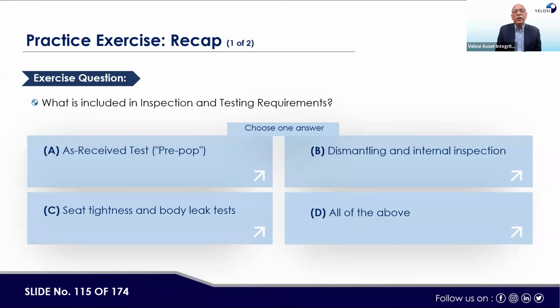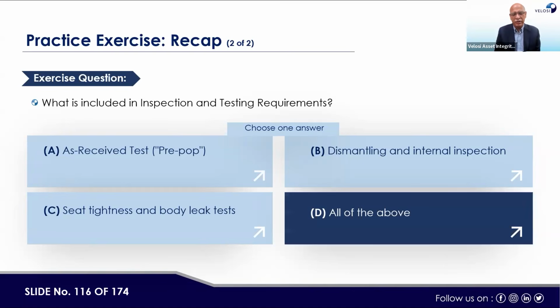The next question: what is included in the inspection and testing requirements of the PSVs? A, as received test, pre-pop. B, dismantling and internal inspection requirement. C, seat tightness and body leak test. This is the minimum requirement in the inspection and test requirements. Most answers are somewhat wrong, but here the as received test is also part of the PSV's inspection and testing requirement. This is a difficult question, and some confusion is there, I can accept. So as received test, pre-pop, dismantling and internal inspection are covered under inspection and testing requirements. C, seat tightness and body leak test are also covered. The answer is D, all of the above. All three are the answer.